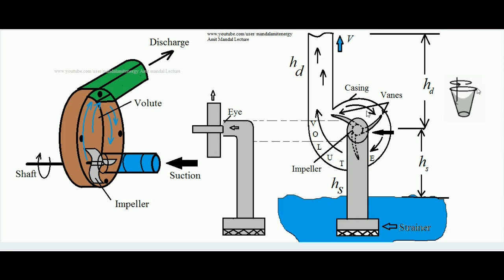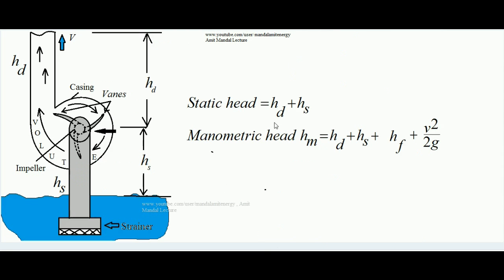When water rotates with the impeller, water is actually thrown to the volute of the centrifugal pump. Over the volute, high pressure water accumulates and due to that high pressure it goes out from the corresponding exit toward the destination. Now, the distance between the center of the impeller and the top surface of the water in the source tank is called the suction head, denoted by HS. The distance from the center of the impeller to the exit of the delivery pipe is called the delivery head. The sum of suction head and delivery head is called the static head of the centrifugal pump.